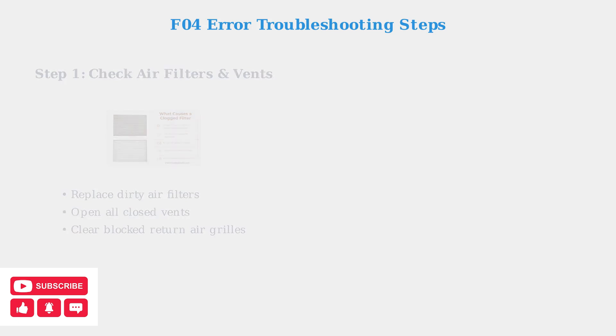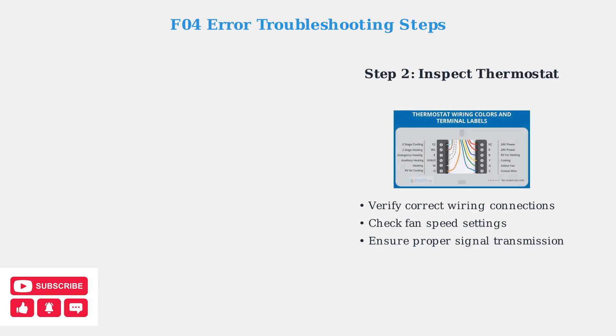When facing a Goodman F04 error, follow these systematic troubleshooting steps to identify and resolve the issue. Start with the most common cause: airflow restrictions. Check your air filters first, as dirty filters are the leading cause of F04 errors. Ensure all vents are open and return air grills are unobstructed. Next, examine your thermostat connections and settings, as loose wiring or incorrect fan speed settings can prevent proper communication with your HVAC system, triggering the F04 error.